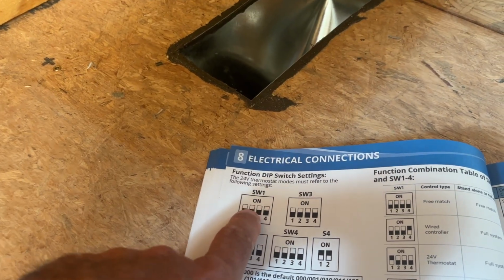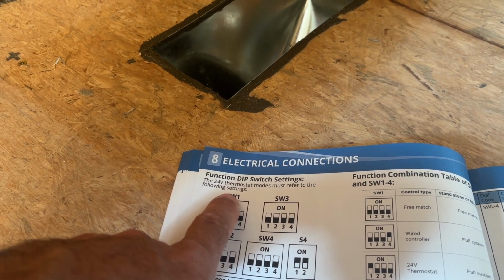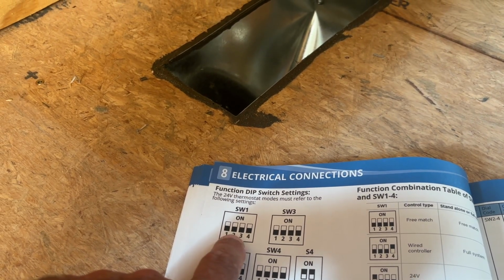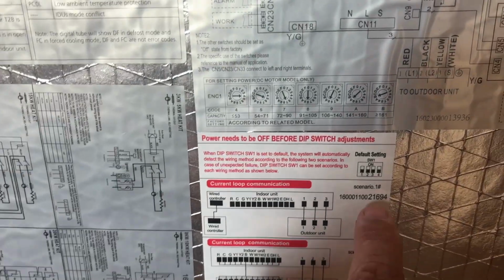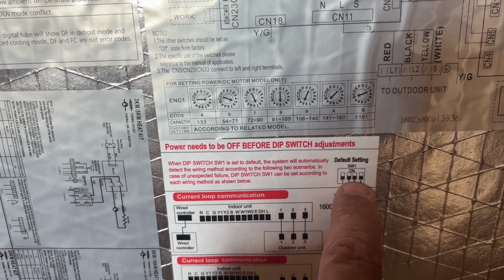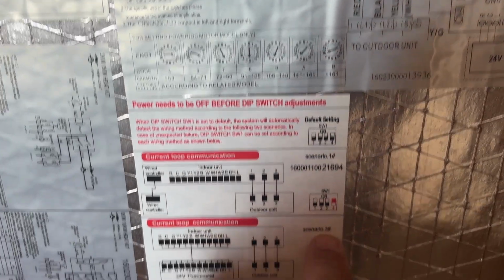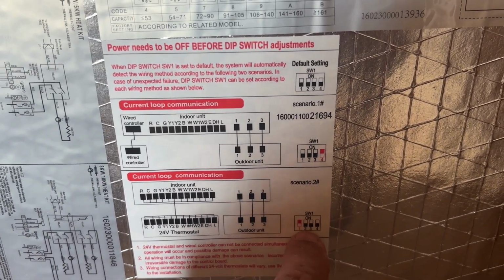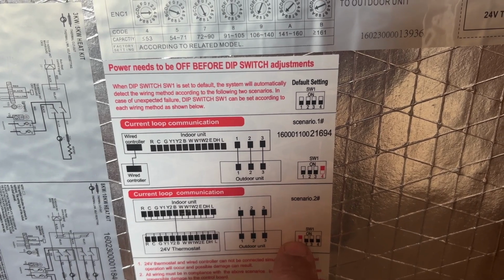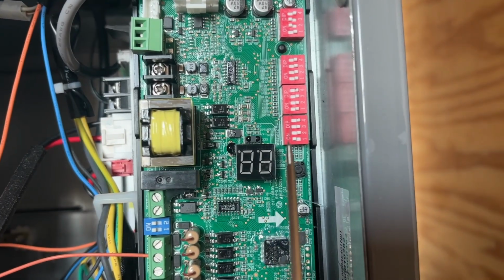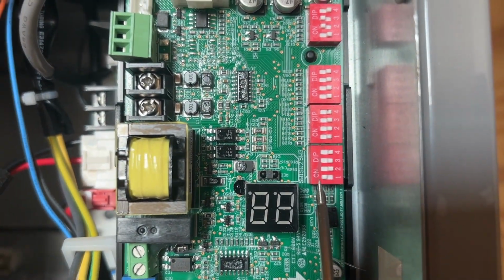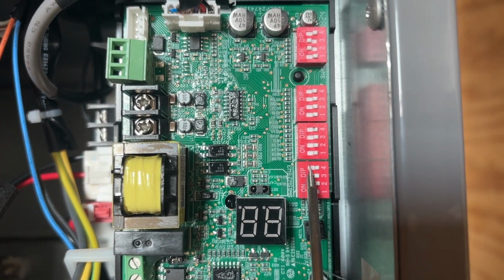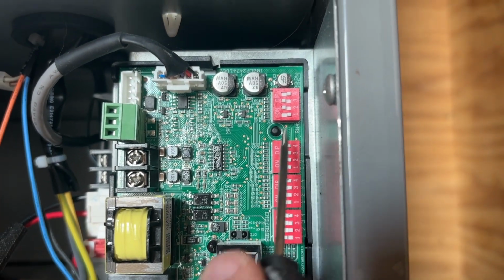The manual shows SW1 for a 24 volt thermostat to be set up with all 4 of the switches in the off position. My unit says I can do that as well. I can put them all 4 off here and let the unit decide that it's a 24 volt system, or I can go ahead and adjust the switch to put SW1-1 in the on position and the other 3 off. And that switch located here at the bottom, you can kind of see what I've done. I've flipped the number 1 to on, 2, 3, and 4 is off. Now I have switch 2, switch 3, and switch 4 here, so let's take a look at those settings.